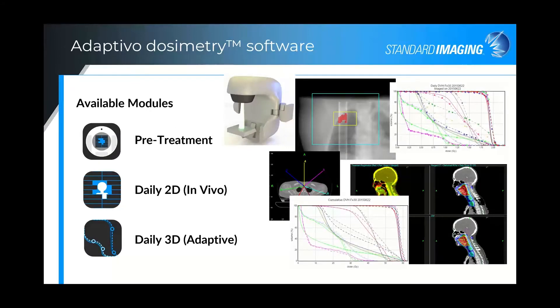Before that, a little background about Adaptivo. There are three available modules. A pre-treatment module, which is useful for cases where you want measurements using your integrated EPID panel for pre-treatment QA — an in-air measurement compared to the predicted image from the RT plan. The second module, the in vivo module, will be the focus of the rest of the webinar. It is very similar to the pre-treatment module, with the exception that the patient anatomy and couch are in the beam.